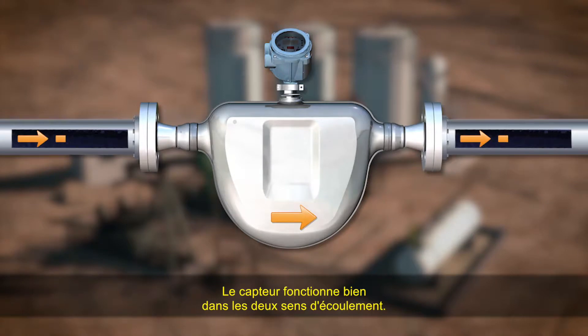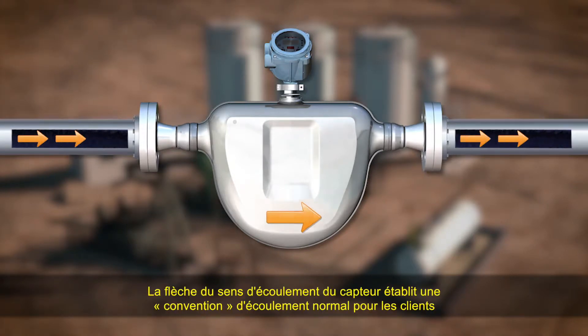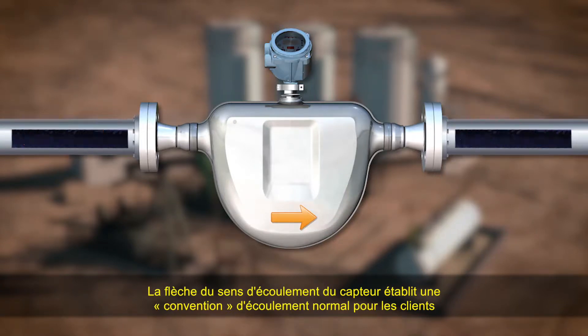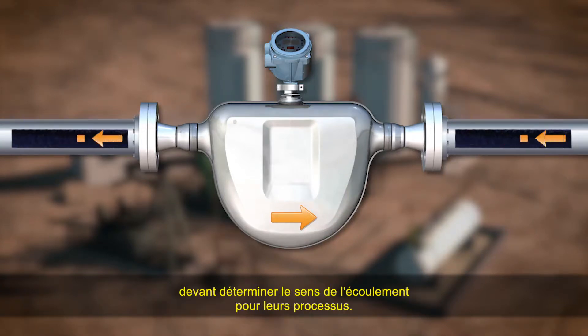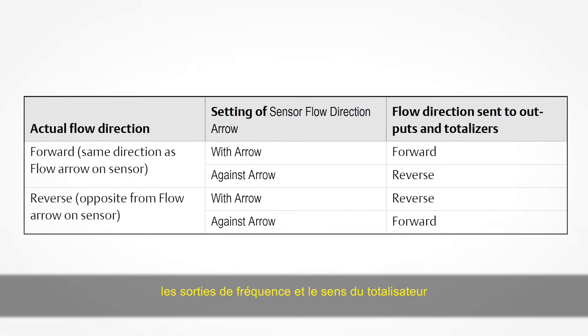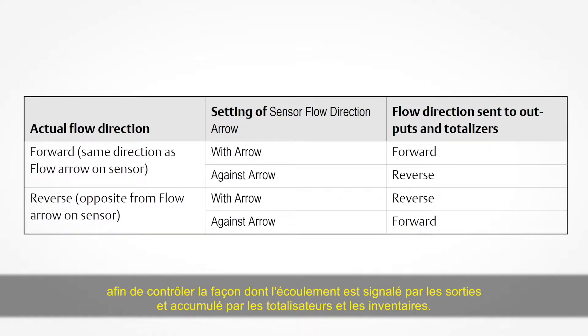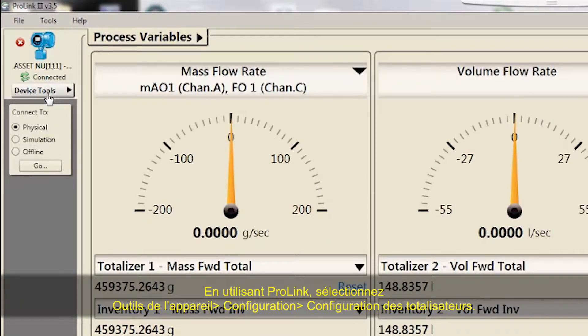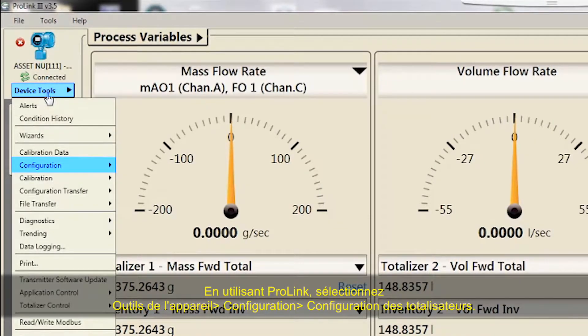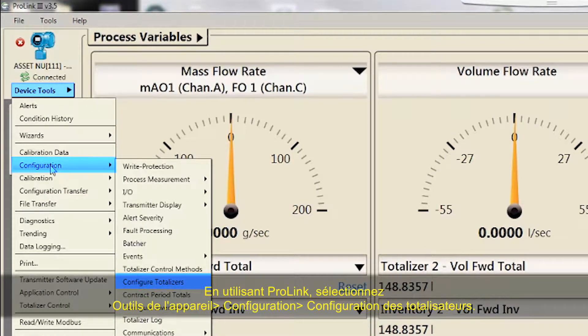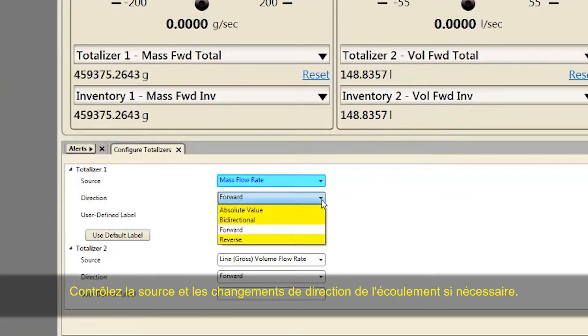The sensor works equally well with flow in either direction. The sensor flow direction arrow establishes a convention of forward flow to accommodate customers who need to define forward and reverse flow for process purposes. It interacts with milliamp outputs, frequency outputs, and totalizer direction to control how flow is reported and accumulated. Using ProLink, select Device Tools > Configuration > Configure Totalizers. Verify the source and change flow direction as needed.